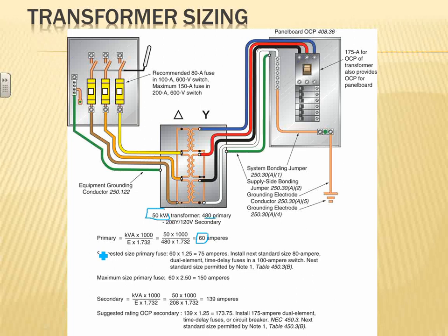Now, suggested size, I want to emphasize the word suggested size here. If you go on the primary 1.25 and on the secondary 1.25, you are right up to 95% of the time. Always. And I'll show you that one with the coordination.